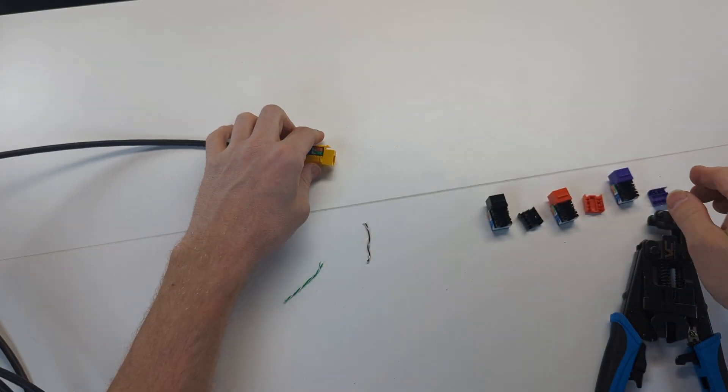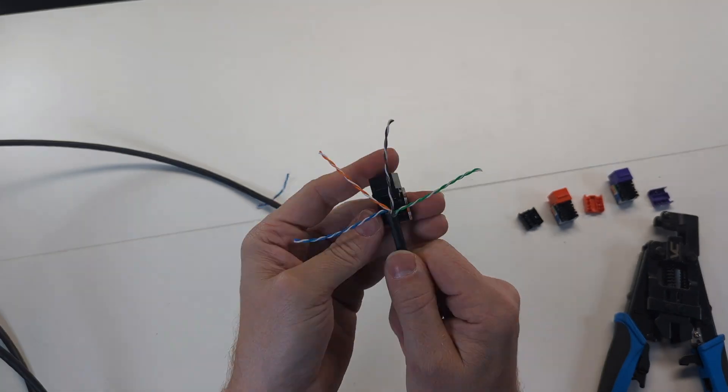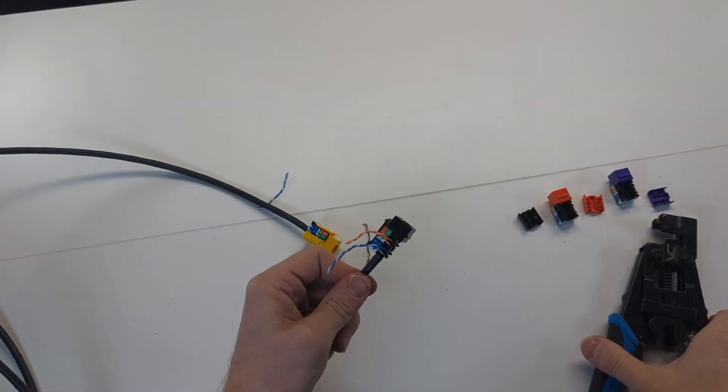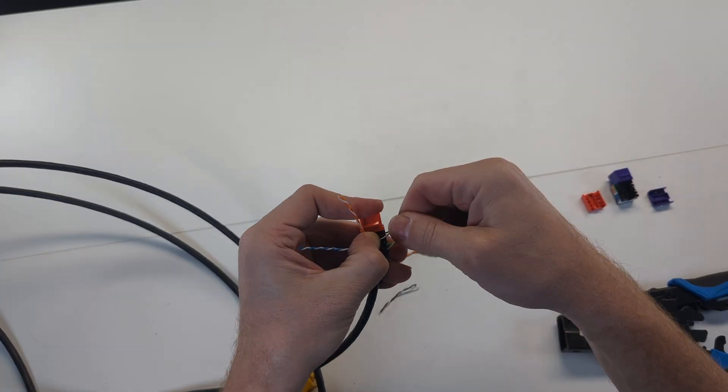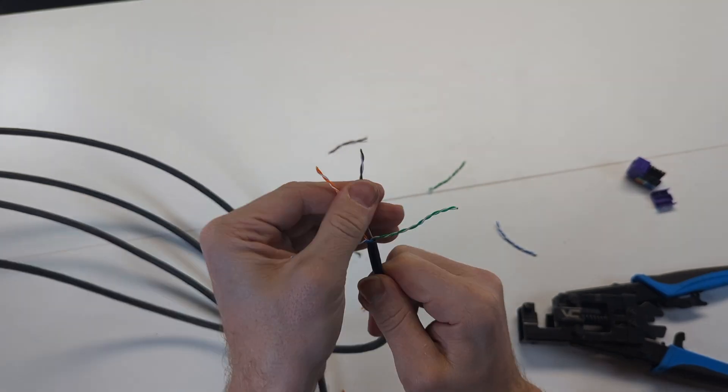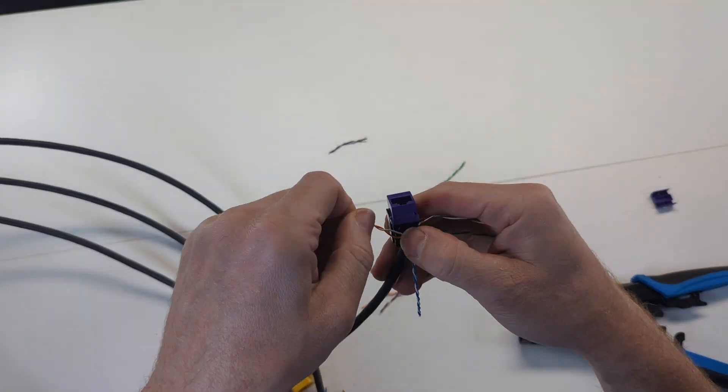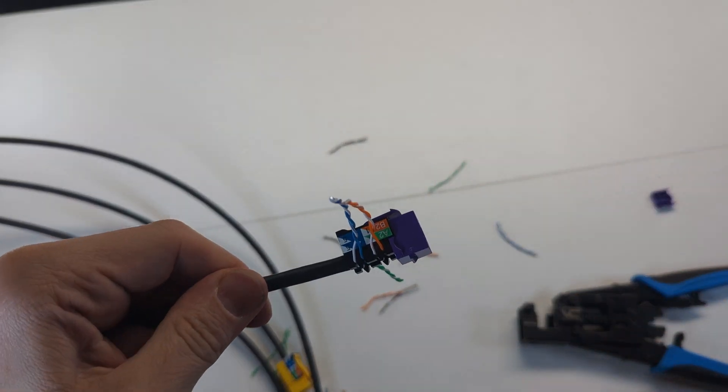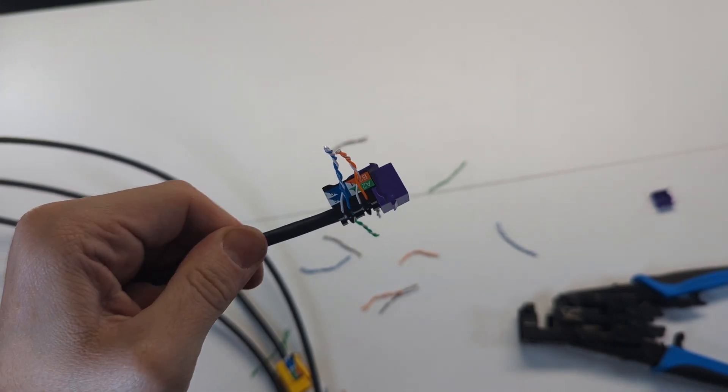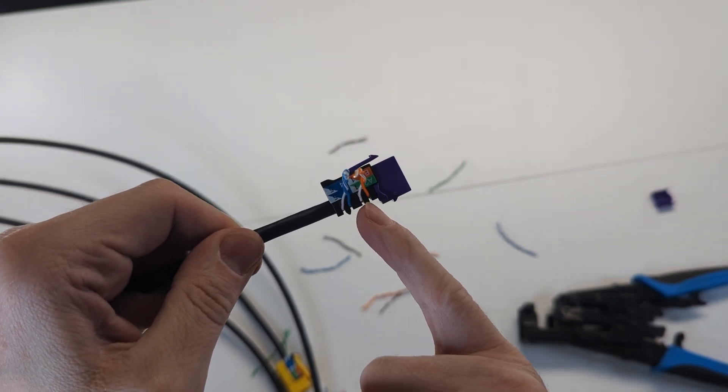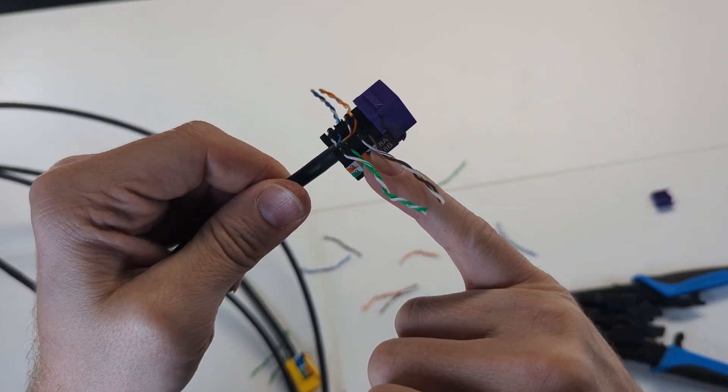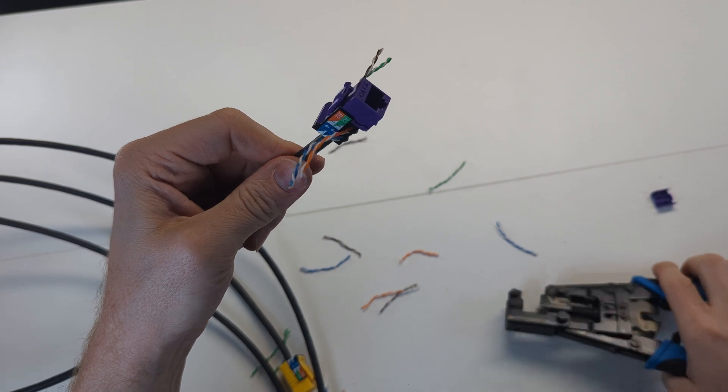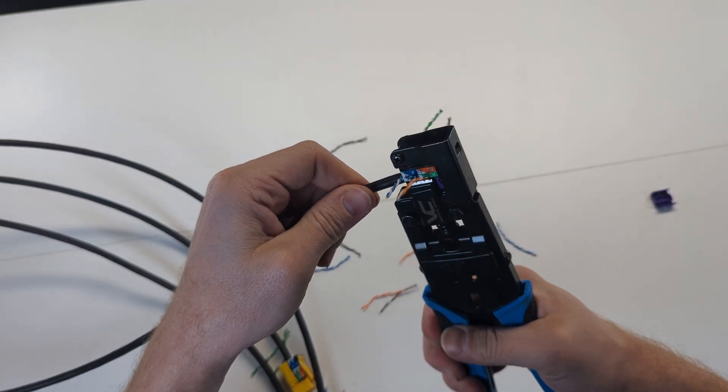We're going to do the same thing with all four jacks. Now before you crimp it or punch it down, it's always good to do a quick visual inspection, making sure I have my white blue, solid blue, white orange, solid orange, white green, solid green, white brown, solid brown. It's better to catch a mistake before you terminate than have to re-terminate.